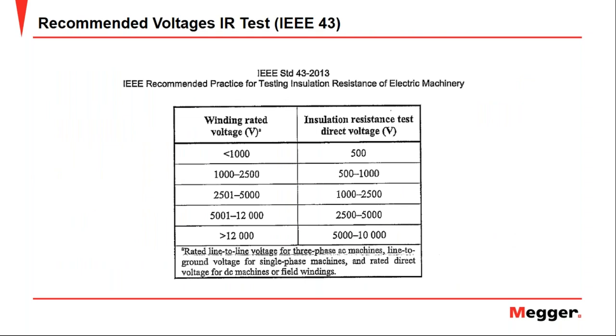So it doesn't matter what the winding rated voltage is, if it is under 1000 volts, you have to do the insulation resistance test at 500 volts. If it is 200, 400, 600, it doesn't matter. You have to do the insulation resistance test at 500 volts. Now, above 1000 volts, we don't have a single number. We have a range, so we can select any value within that range, okay? You can select the minor value or the maximum value or the average value. It's up to you. The important thing is that the value that you choose is within this range.